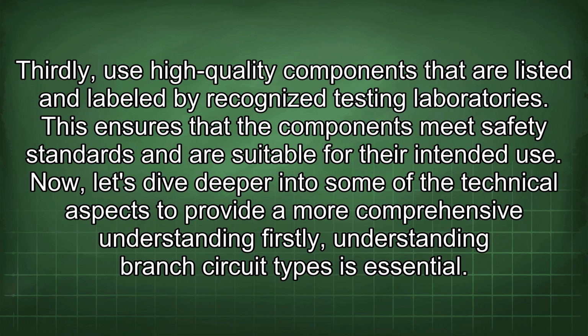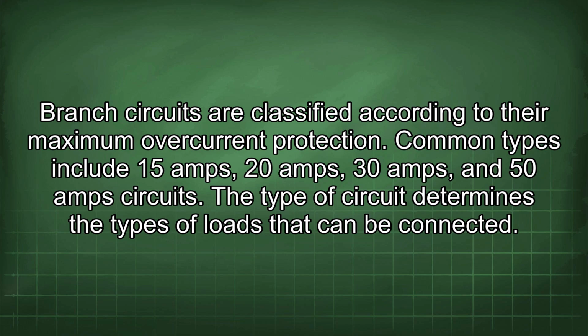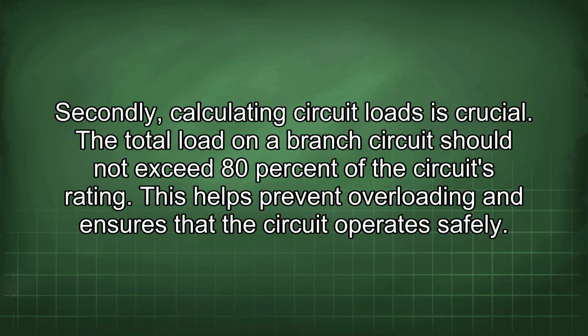Now, let's dive deeper into some of the technical aspects to provide a more comprehensive understanding. Firstly, understanding branch circuit types is essential. Branch circuits are classified according to their maximum overcurrent protection. Common types include 15 amps, 20 amps, 30 amps, and 50 amp circuits. The type of circuit determines the types of loads that can be connected. Secondly, calculating circuit loads is crucial. The total load on a branch circuit should not exceed 80% of the circuit's rating. This helps prevent overloading and ensures that the circuit operates safely.